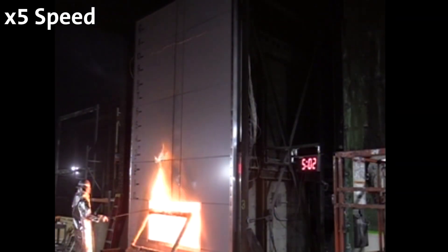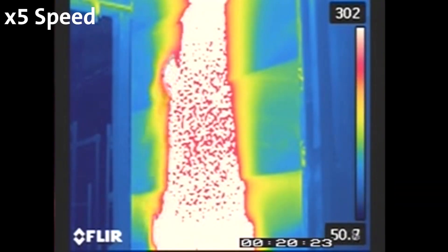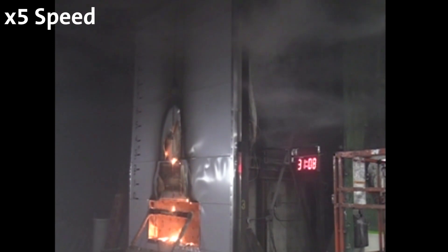At five minutes, we ignite the window burner. At eight minutes, we see warping at the panels about three feet up from the opening — similar to the first test. This test passed NFPA 285 for the complete 30-minute duration, complying with both the temperature requirements and the flame propagation requirements — very different from the first test that was stopped at 16 minutes. This showed acceptable performance, with the only change between the two assemblies being the ACM panels.